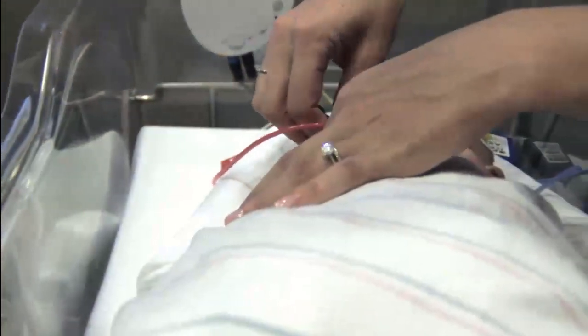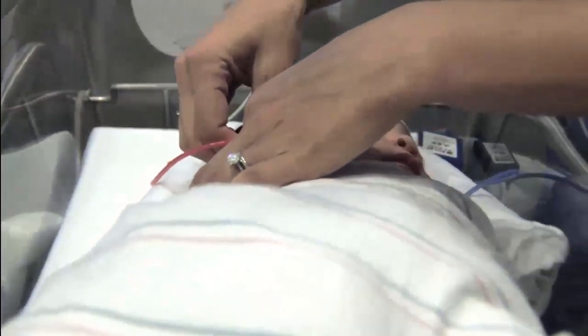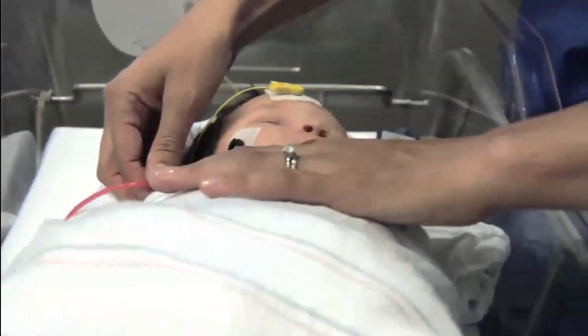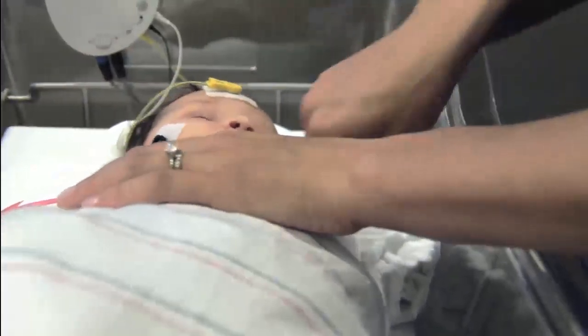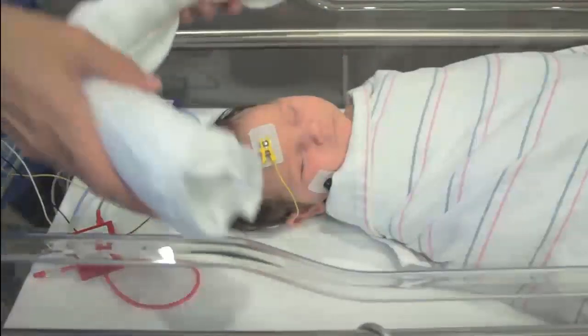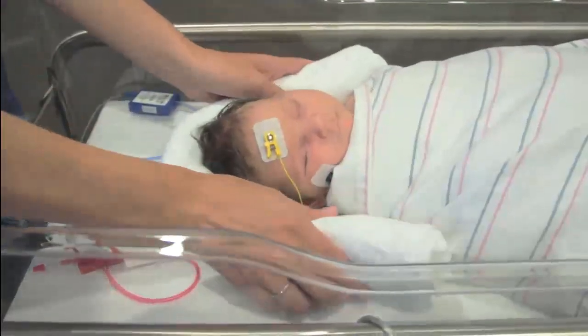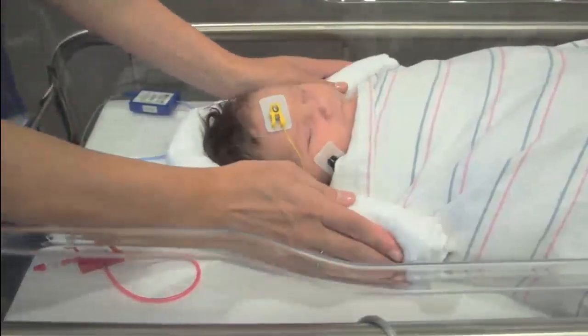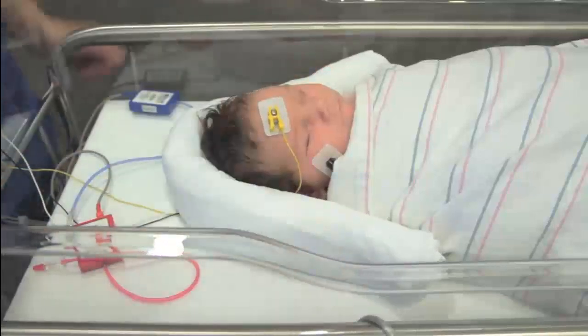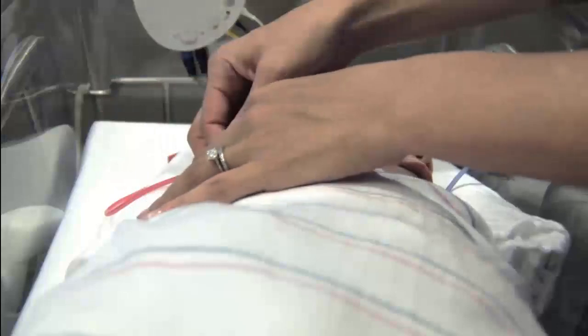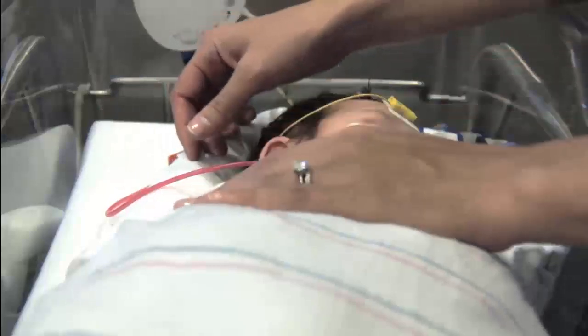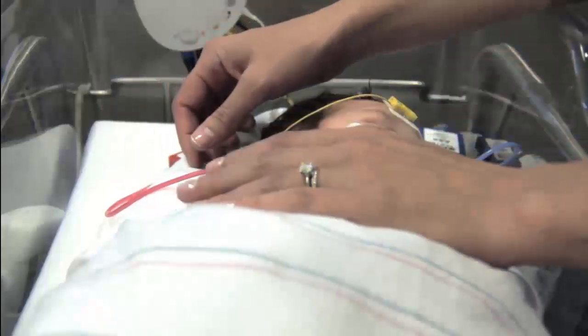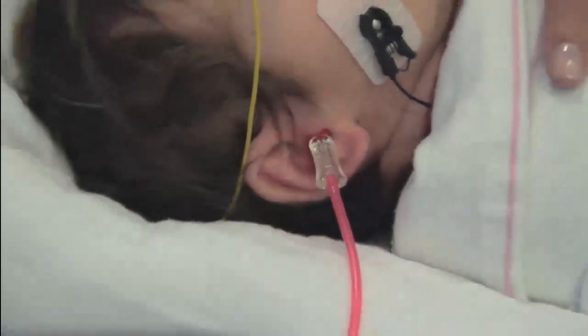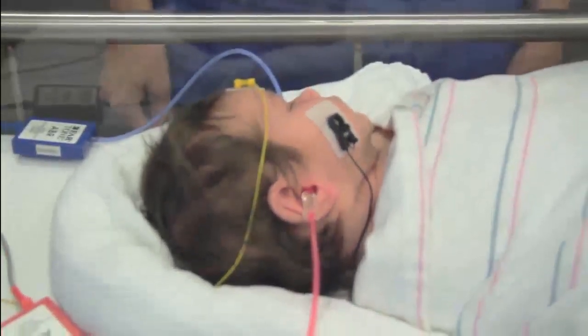It may be a challenge, however, to keep both ear tips securely inserted into the baby's ear for a binaural or both ears screening. Rolling a small blanket and positioning it around the top of the baby's head may help to prevent the baby from turning her head, dislodging one of the ear tips. If a binaural test cannot be performed because of the baby's position, screen each ear individually. When the baby is prepped and quiet, start the measurement.